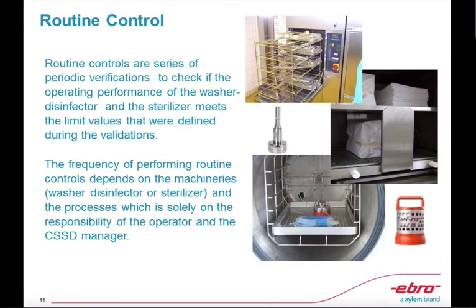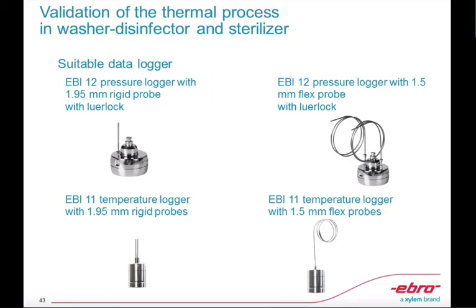Not all of you may know about routine control, which is different from validation — this is more frequent. This process is a series of periodic verifications to check if everything is working, not only with the washer disinfectors and sterilizers (autoclaves), but also the different machineries in the CSSD and the hospital. The frequency of performing routine controls depends on the machineries and processes, and is solely the responsibility of the assigned operator and managers.